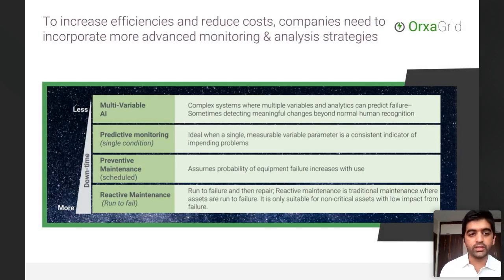A level above that, requiring a little more capital investment, is preventive maintenance, the most widely adopted strategy. This is condition-based or time-based maintenance, where every 6 months you take the asset out of service and perform some maintenance. If your asset is a transformer, you'd do things like ratio measurement or winding resistance measurement, run your tests, certify that it's operating within permissible limits, and then put it back into service. So there's still some downtime on the asset side, as well as a cost for doing the maintenance on a timely manner.